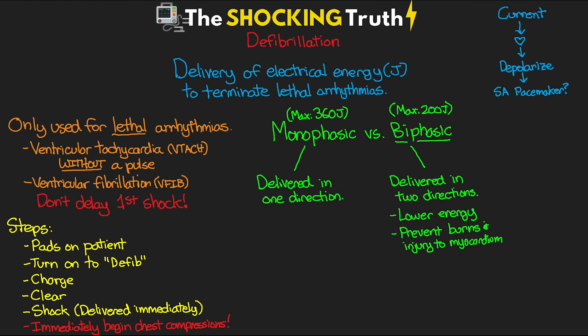The maximum energy for monophasic is 360 joules, while for biphasic the maximum is only 200 joules. Current recommendations are to deliver the shock and then immediately resume chest compressions. The recommended energy steps for the initial and each successive shock for adults start at 120 joules, then 150 joules, then 200 joules — and any successive shocks after that continue at 200 joules. For internal defibrillation, much less energy is used: starting at 5 joules, then 10, 20, 30, and finally 50 joules, staying at 50 if you reach that point.